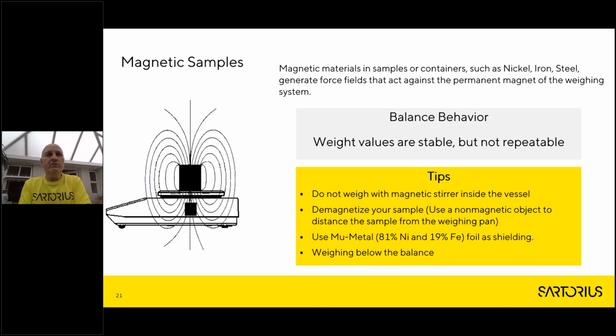Magnetic samples can also have an influence on our weighing process. If you think about the weighing cell in a balance, this is built by using a magnet. The whole process is electromagnetic force compensation. That's how our weighing cell works. So anything which is magnetically charged will be influencing the magnet in our weighing cell and creating an error in the weighing process. So the behavior of the balance is that the weight values will be stable, but they will be incorrect and they will not be repeatable.